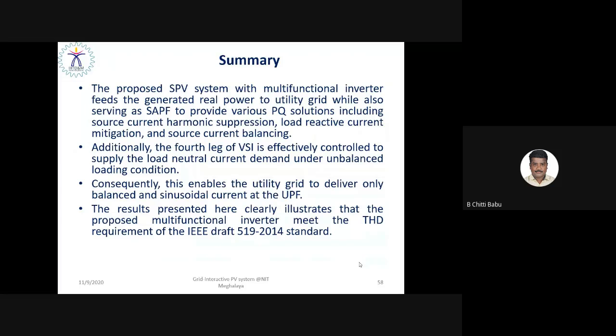Okay, so the summary is that the proposed solar PV system with a multifunction inverter feeds controllable active as well as reactive power into the utility grid. Moreover, it also acts as a shunt active power filter, filtering out the unnecessary harmonic components injected into the utility grid, so that overall the grid current waveform becomes sinusoidal, with THD less than 5% as per the IEEE 519/2014 standard, right?